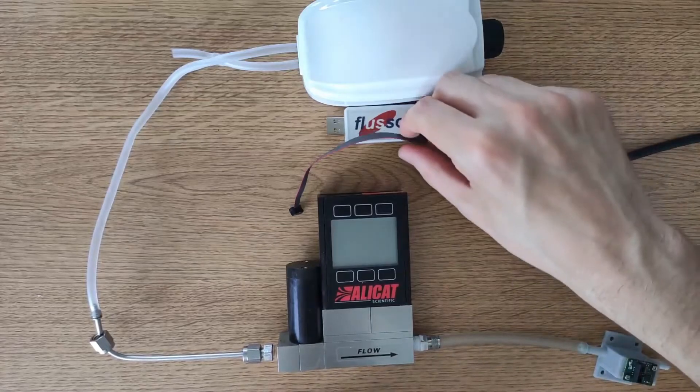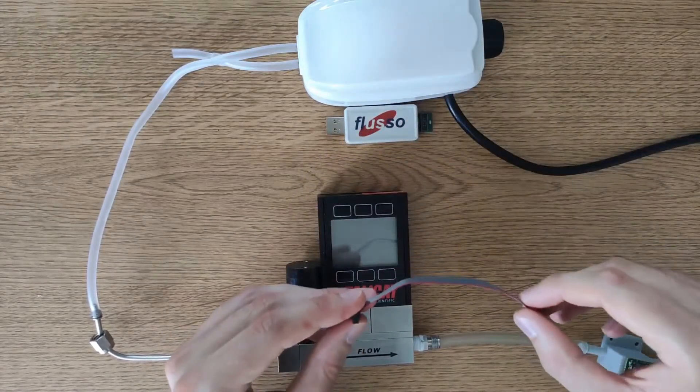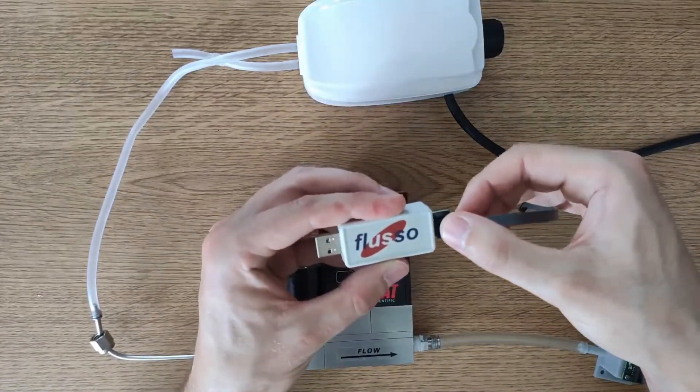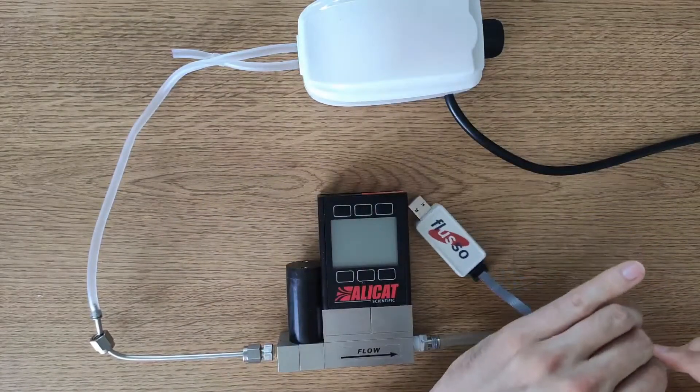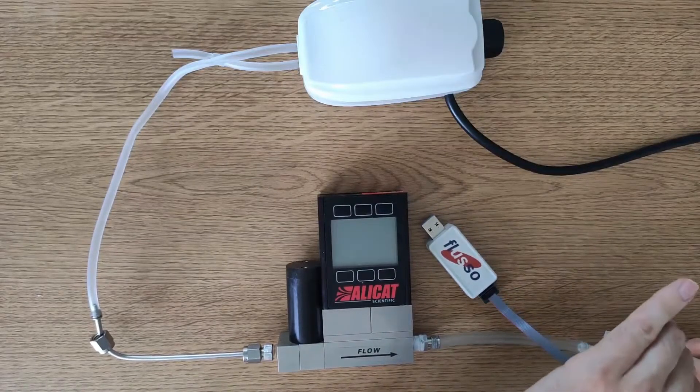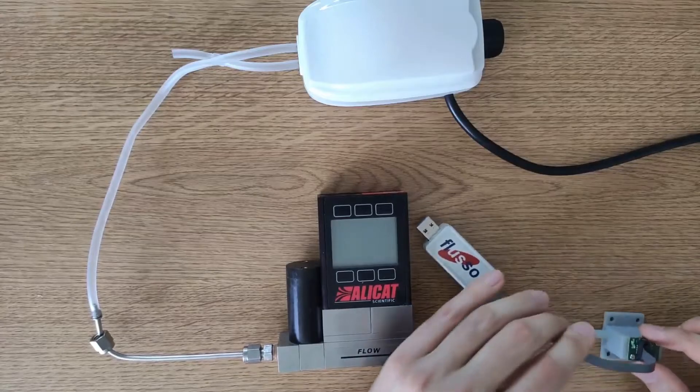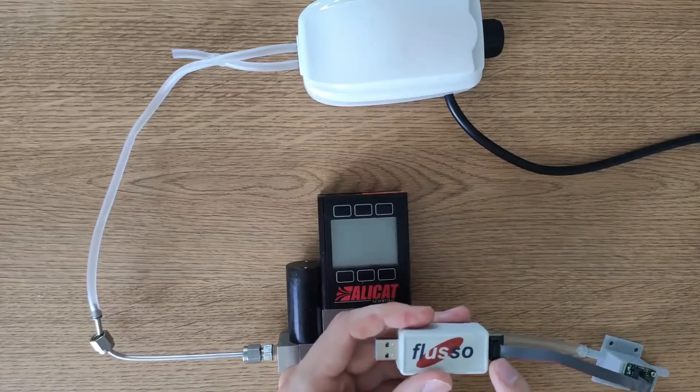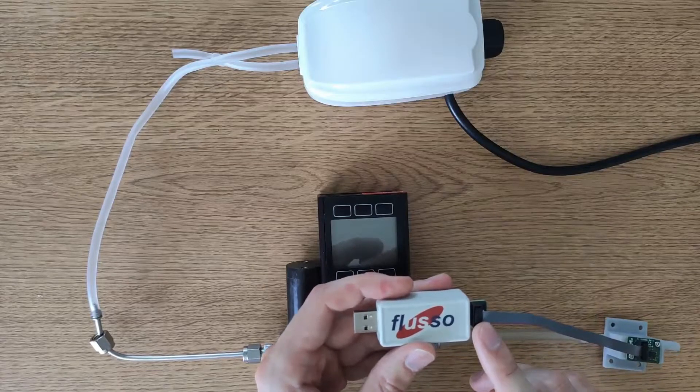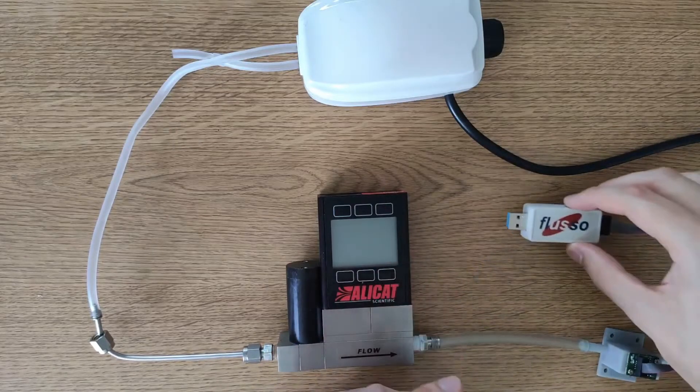We need to make the electrical connection and this is going to be done by using this cable here. We're going to connect one end of the cable to the USB to I2C adapter and the other end to the FLS110 sensor module. Don't worry about getting the orientation of the connector wrong because this is a keyed connector so you can only put it in one way round and that way round is the correct way round. Once you have this set up you can plug it into your laptop. I've got this simple USB extender cable here so I'll just use that.